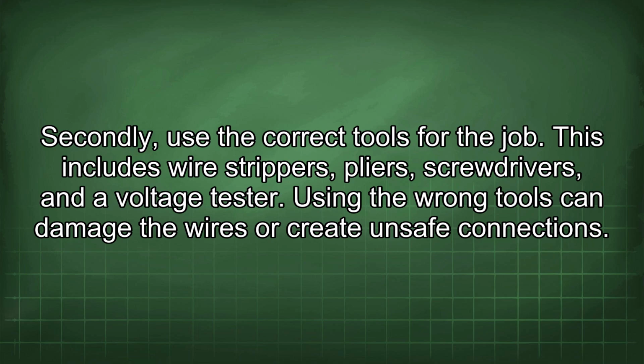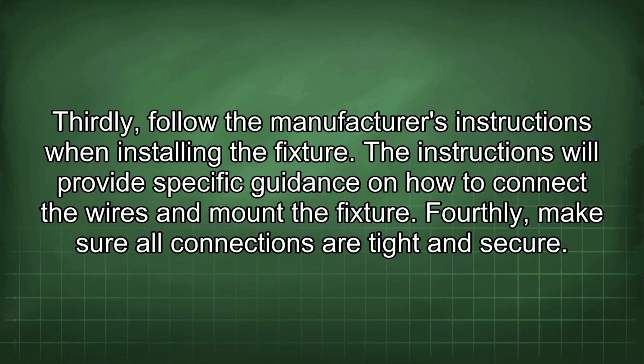Secondly, use the correct tools for the job. This includes wire strippers, pliers, screwdrivers, and a voltage tester. Using the wrong tools can damage the wires or create unsafe connections. Thirdly, follow the manufacturer's instructions when installing the fixture. The instructions will provide specific guidance on how to connect the wires and mount the fixture.